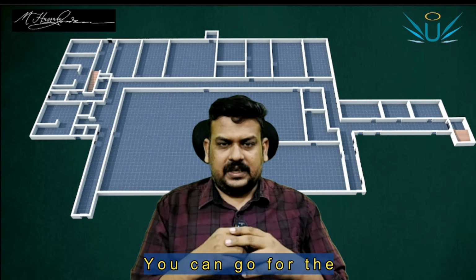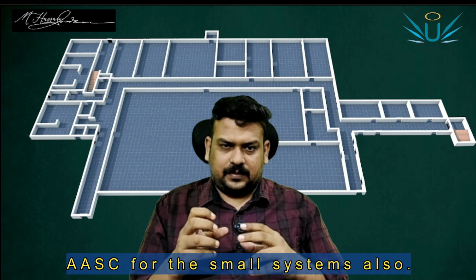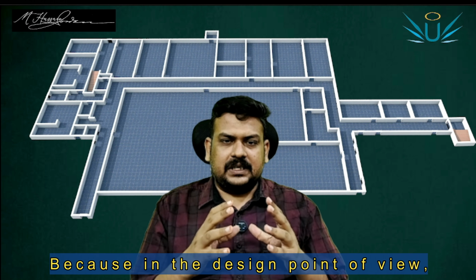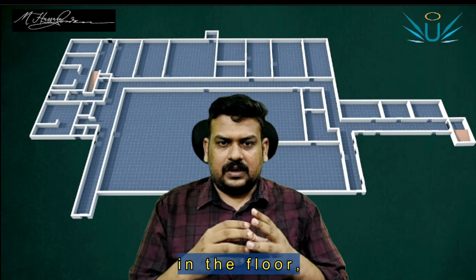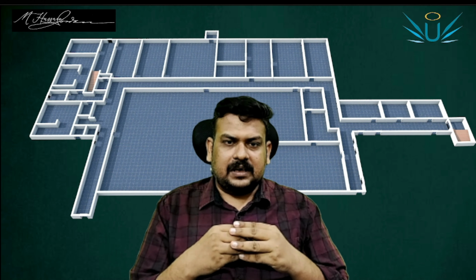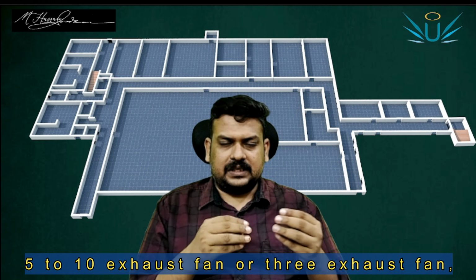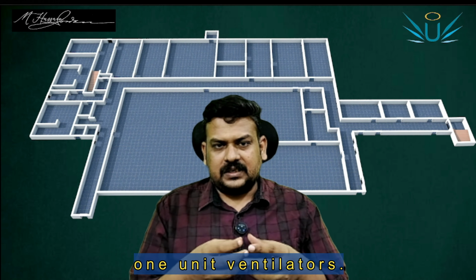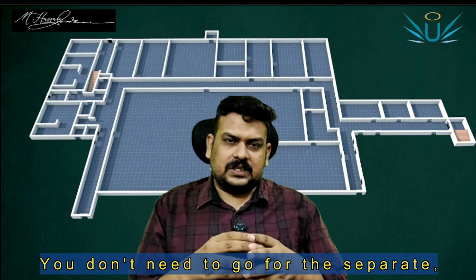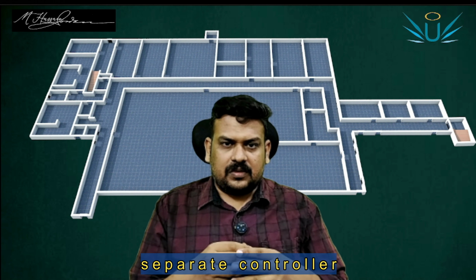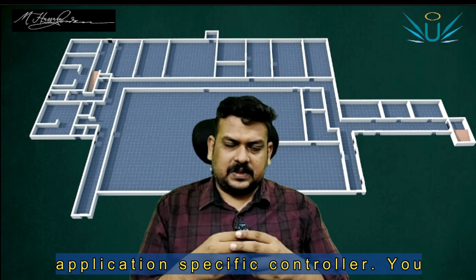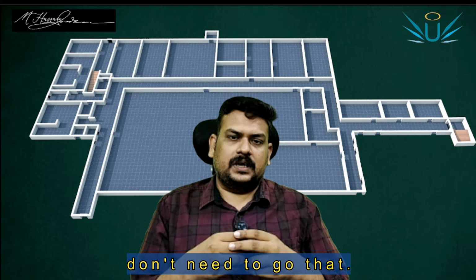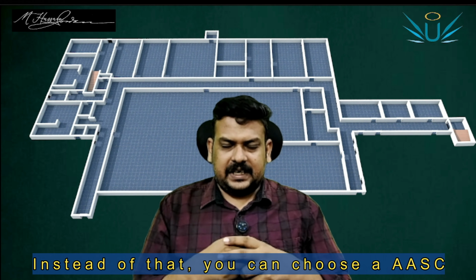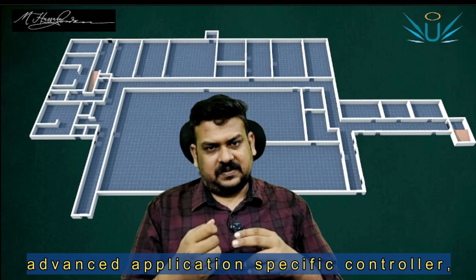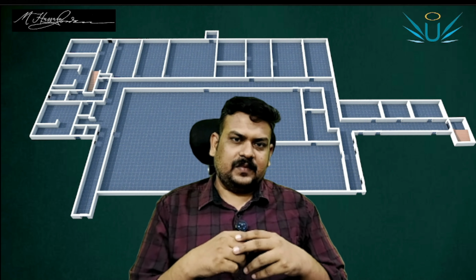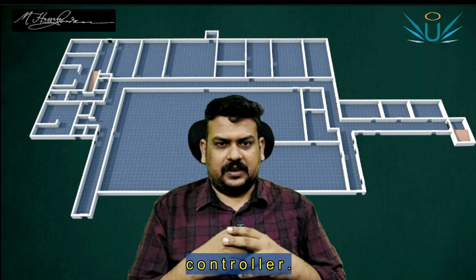You can go for the AASC for the small systems also, because from the design point of view, on a floor you may have 5 to 10 exhaust fans, or 3 exhaust fans and 1 unit ventilator. You don't need to go for a separate controller like an application specific controller. Instead of that, you can choose the AASC, the advanced application specific controller, and combine the program logic in that particular controller.